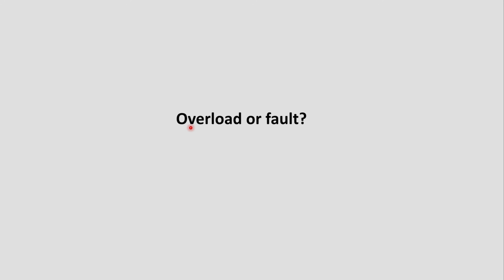Now I need to decide, am I protecting for an overload or a fault? And you might be thinking, but isn't an overload a fault, and isn't a fault an overload? An overload may be considered a fault if you designed it like that, but usually a fault has a much higher rise in current than an overload.